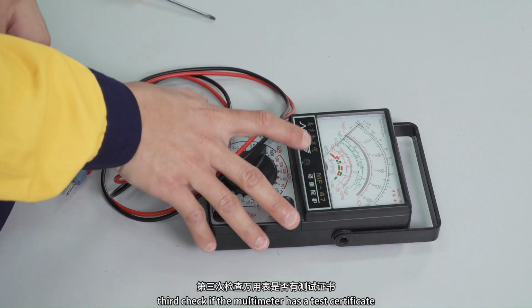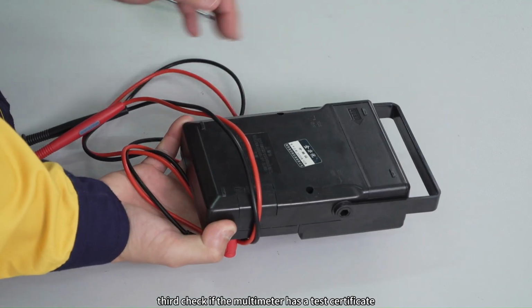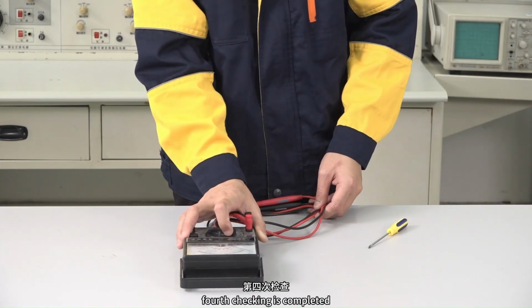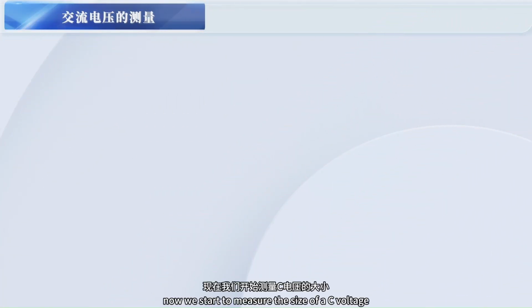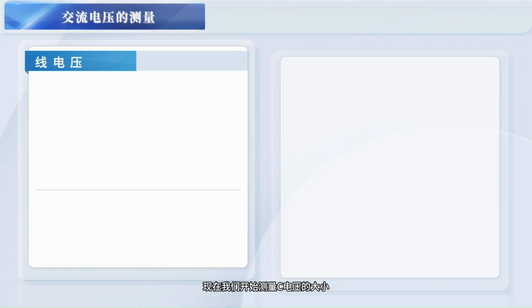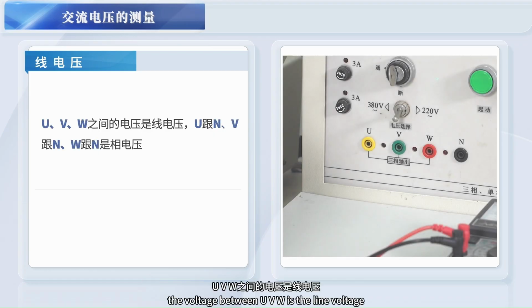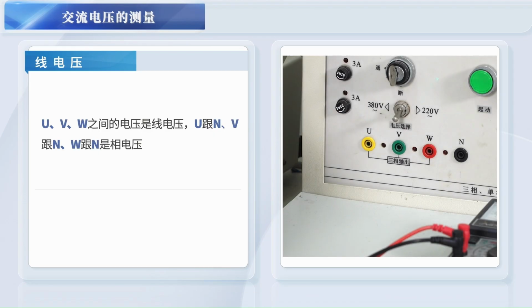Third, check if the multimeter has a test certificate. Fourth, checking is completed. Now we start to measure the size of an AC voltage. The voltage between U, V, and W is the line voltage. The voltages of U to N, V to N, and W to N are phase voltages.